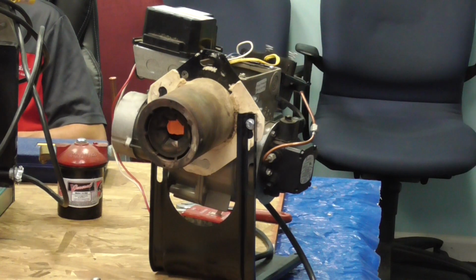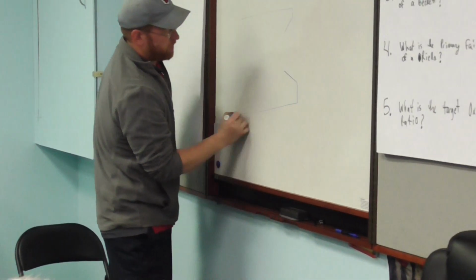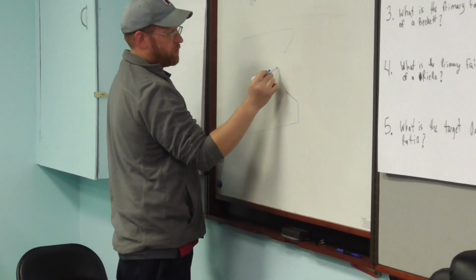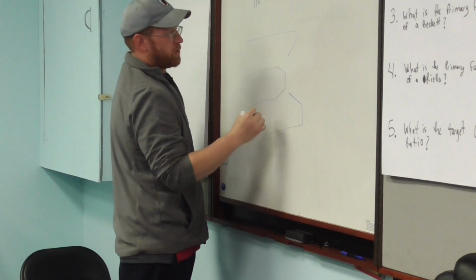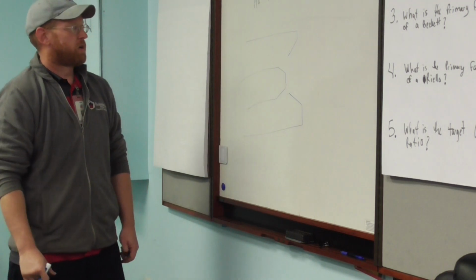You'll have a ton of soot and oil residue on the burner. Your flame ain't even gonna go on. I thought it was probably the oil coming back. The oil comes back, I wanna try to spray, it's not gonna make it inside the chamber.